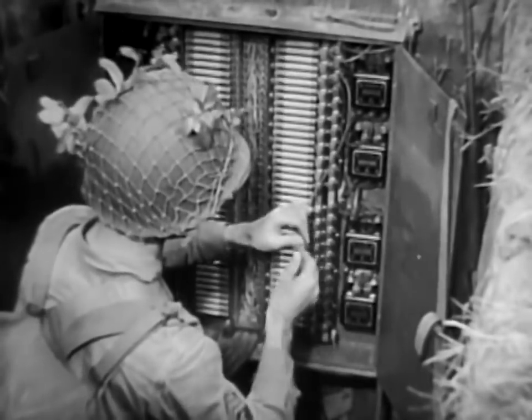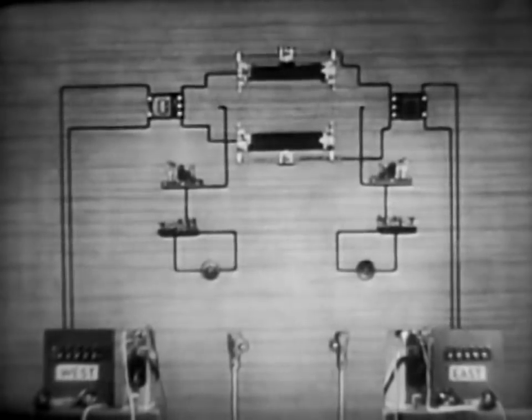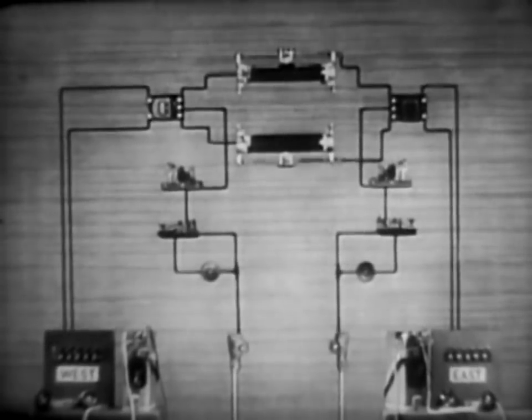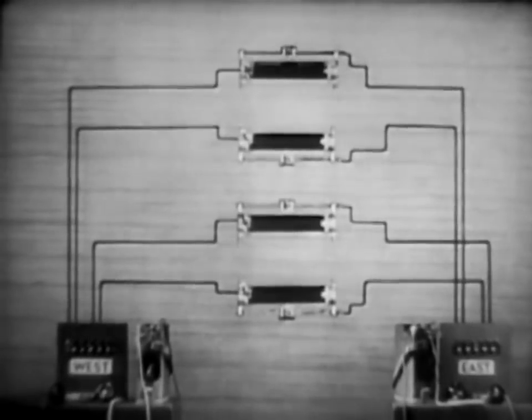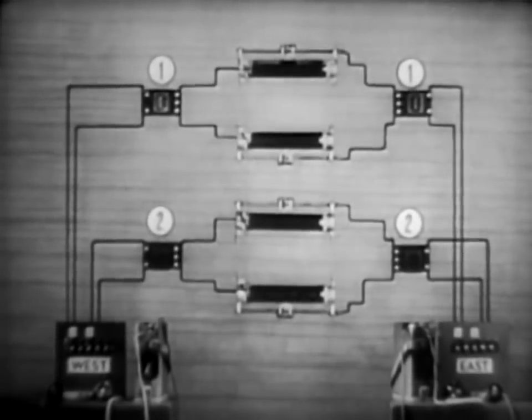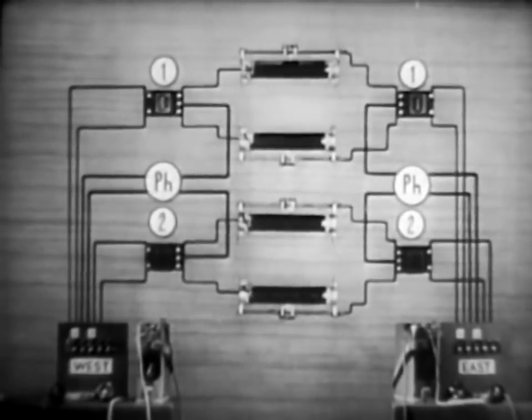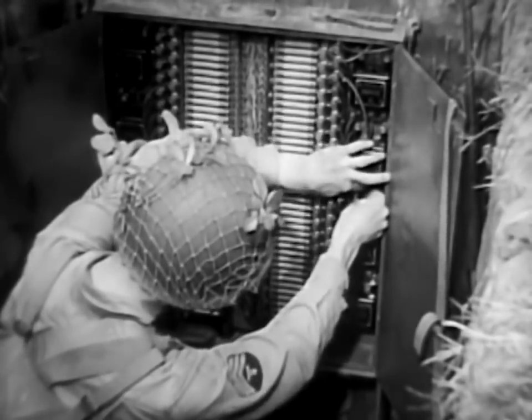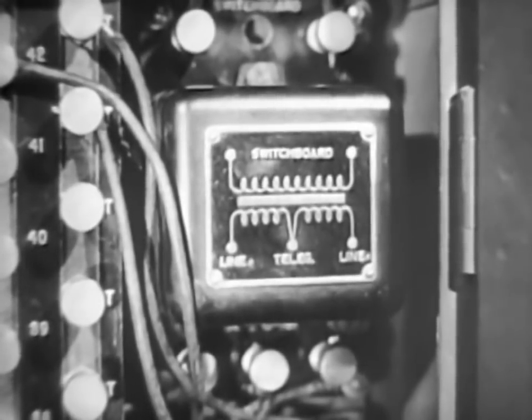Simplex and phantom circuits are used extensively throughout the army. Every wire man should know how they work. The simplex circuit is obtained by connecting repeating coils at both ends of a line and using the earth as a return conductor. The phantom circuit is obtained by connecting repeating coils at both ends of two lines. Instead of using one telephone line and the earth as conductors, the phantom uses two telephone lines. Because simplex and phantom circuits increase the telephone and telegraph capacity of existing lines, the proper use of repeating coils eliminates the trouble, danger, and time of laying miles of extra wire.